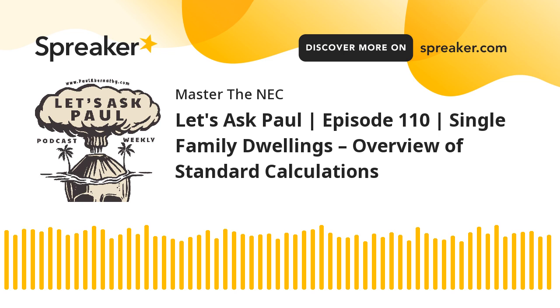However, if the heat still beat the AC in the previous step and we discounted the AC, now that's gone. So now you've got to go searching for the largest other motor in the dwelling. And that might be the trash compactor, right? And so you're going to take that value times 25%. And all we're trying to do is capture that additional 25%. That's all we're trying to do.